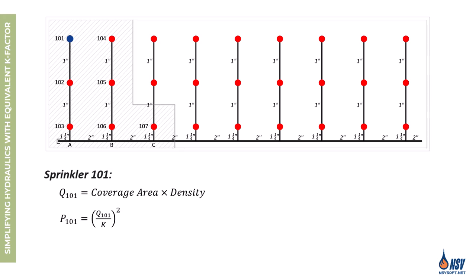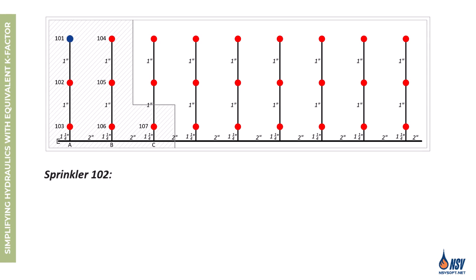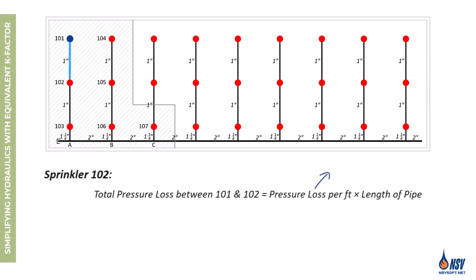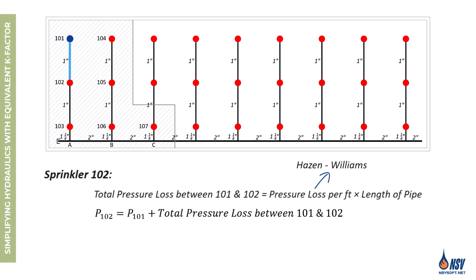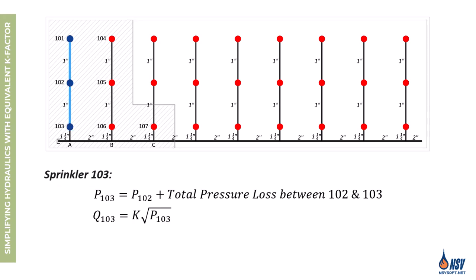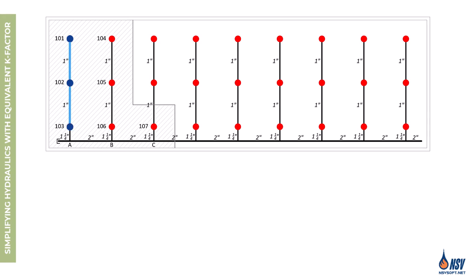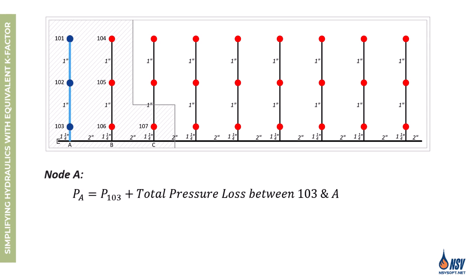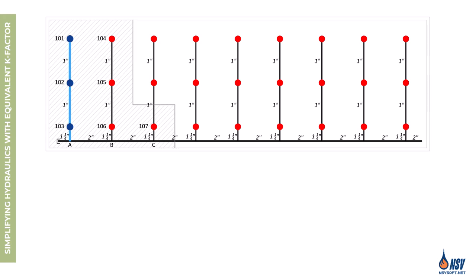For sprinkler 101, we calculate the flow rate by multiplying its coverage area by the required density. Once we have the flow rate, the pressure is determined by dividing the flow rate by the K factor and squaring the result. We then move on to sprinkler 102 — the pressure loss in the pipe between these two sprinklers is determined using the Hazen-Williams formula. Once we know that loss, we find the pressure at sprinkler 102 and calculate its flow rate. We continue this step-by-step process for sprinkler 103, then determine the pressure at node A, which represents the intersection between the most remote branch line and the cross main.